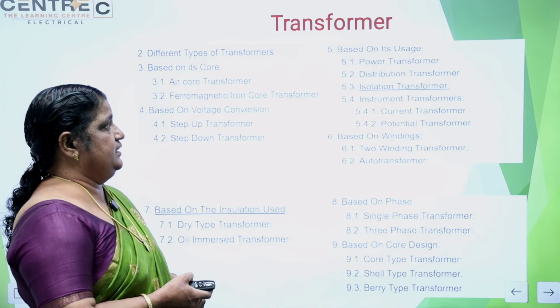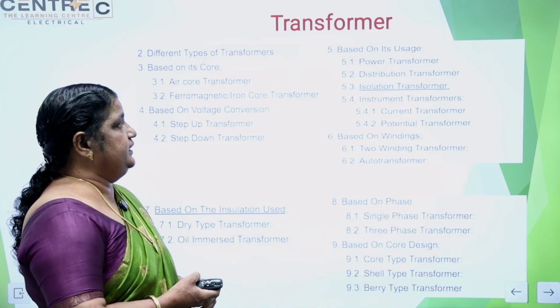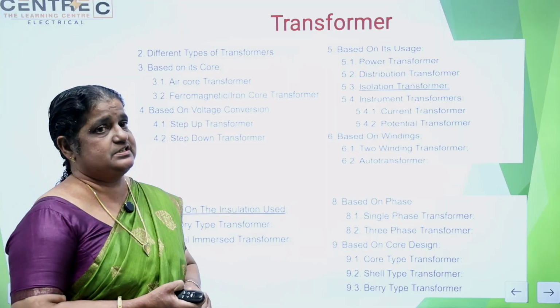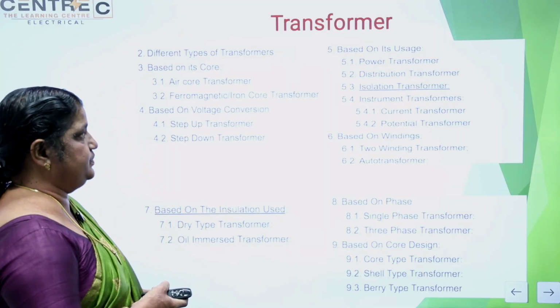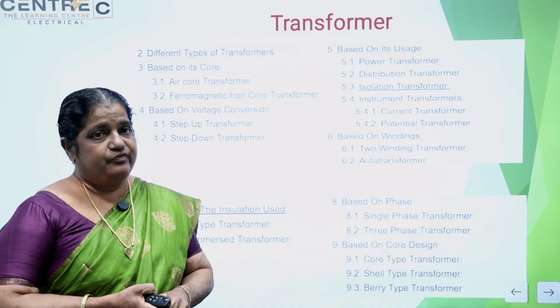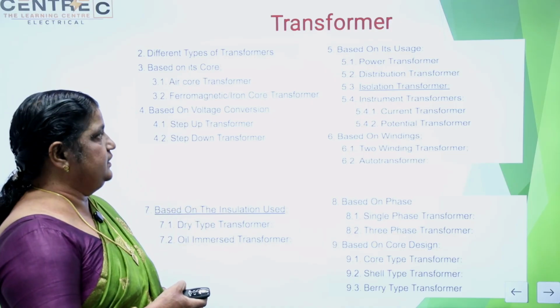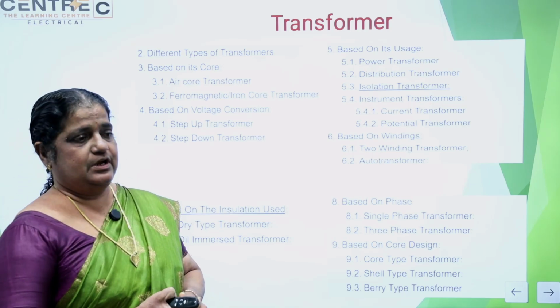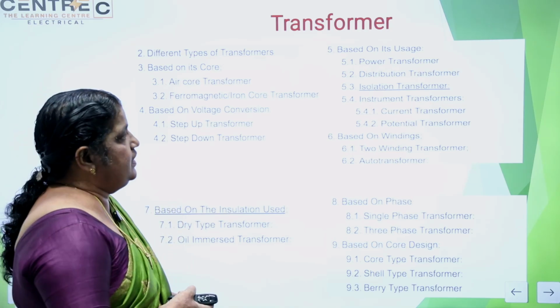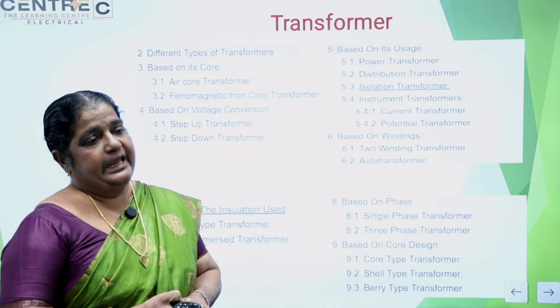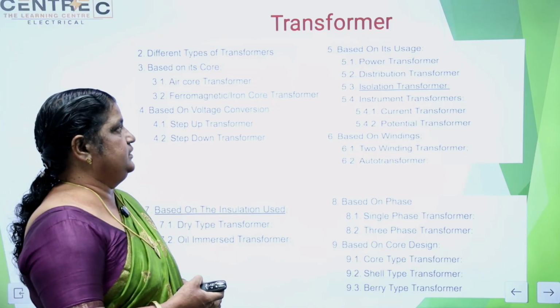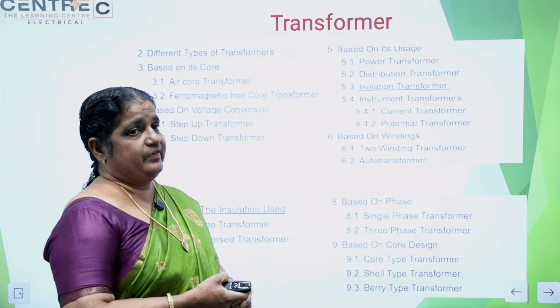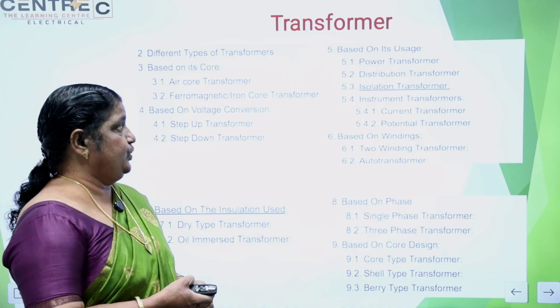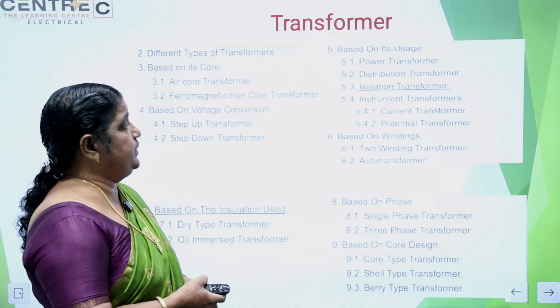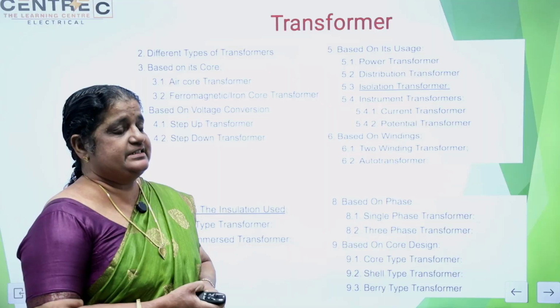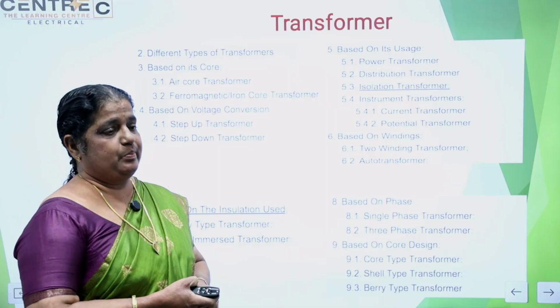In industry, we use it as a power transformer. Then in the power system, that is the distribution system, the roadside transformer is called a distribution transformer. For efficiency, in the case of a power transformer, efficiency equals output power divided by input power. But in the case of a distribution transformer, it is all-day efficiency, output energy divided by input energy. Then the isolation transformer is used for power isolation, that is, its ratio is 1:1. In the case of power transformer and distribution transformer, the ratio is less than 1 or greater than 1, depending upon step up or step down.